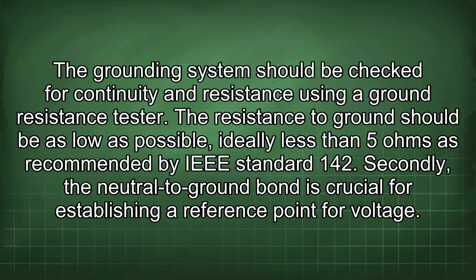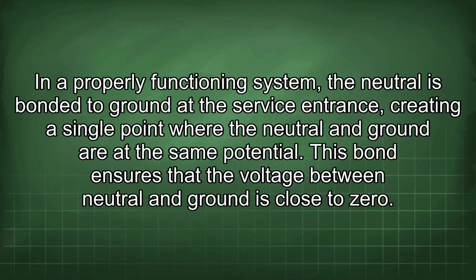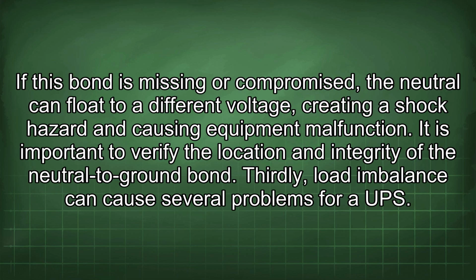142. Secondly, the neutral to ground bond is crucial for establishing a reference point for voltage. In a properly functioning system, the neutral is bonded to ground at the service entrance, creating a single point where the neutral and ground are at the same potential. This bond ensures that the voltage between neutral and ground is close to zero. If this bond is missing or compromised, the neutral can float to a different voltage, creating a shock hazard and causing equipment malfunction. It is important to verify the location and integrity of the neutral to ground bond.